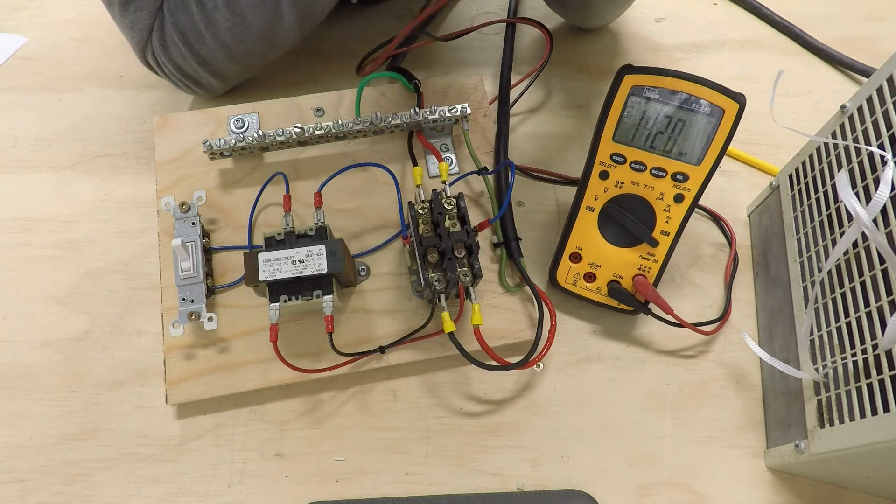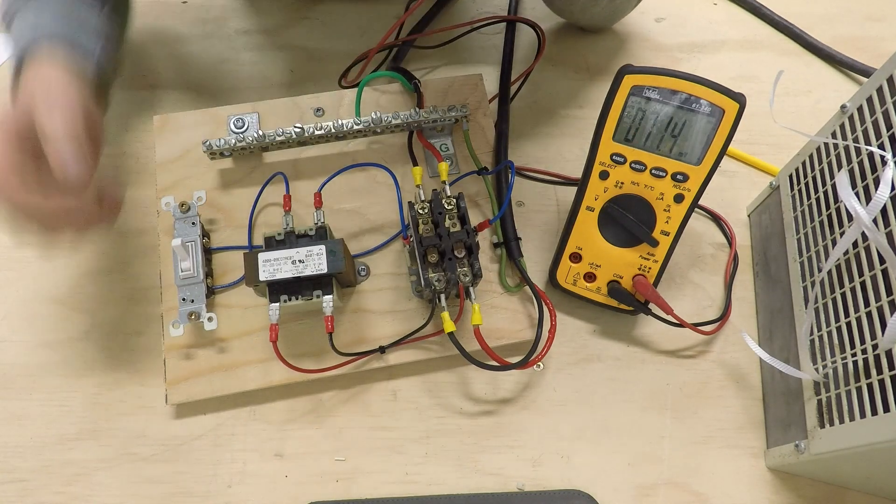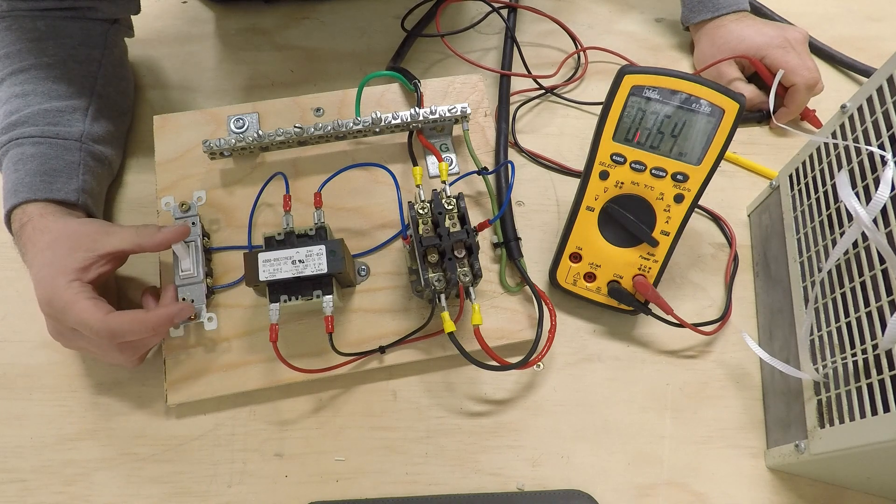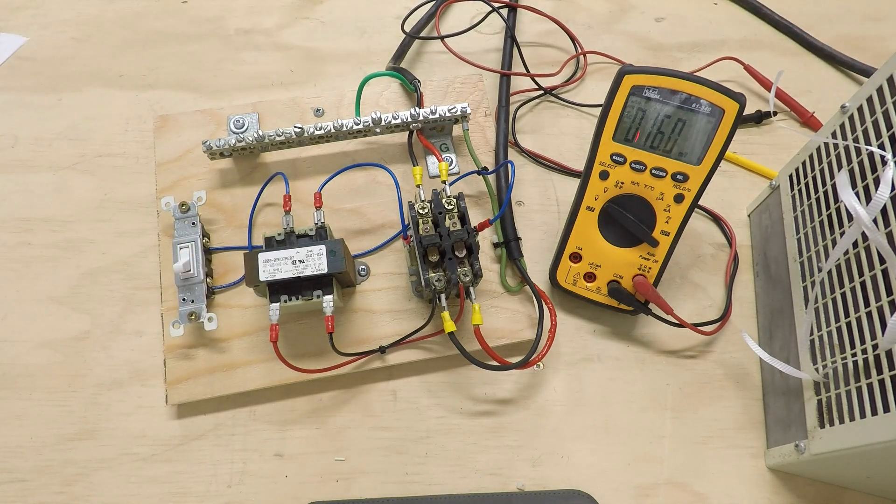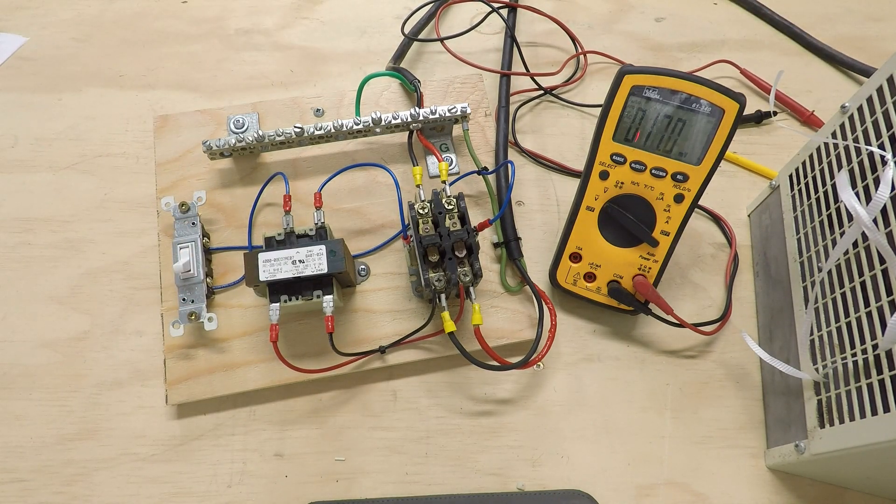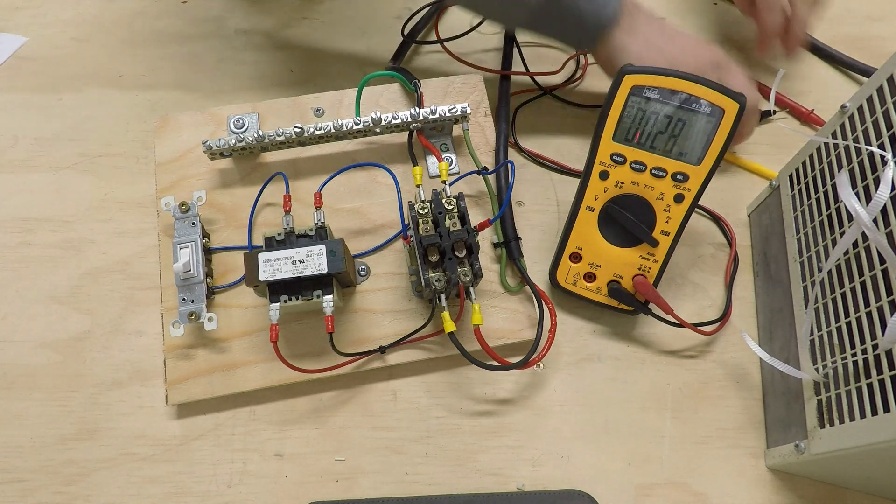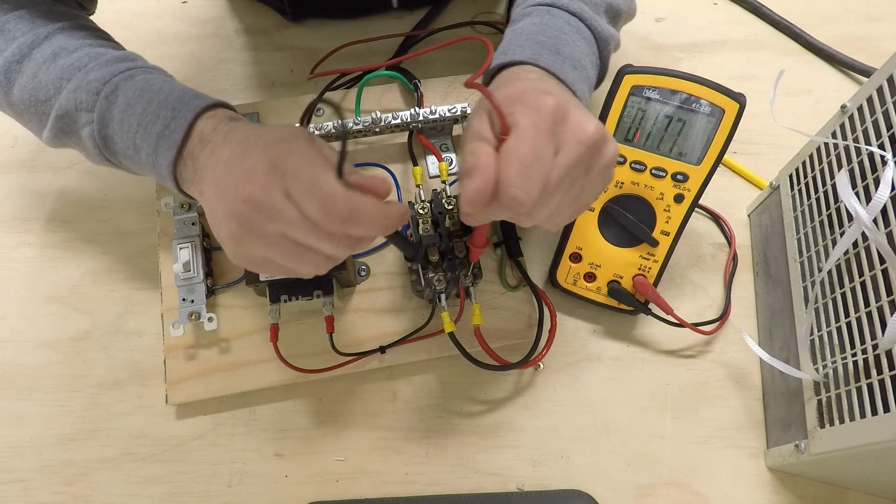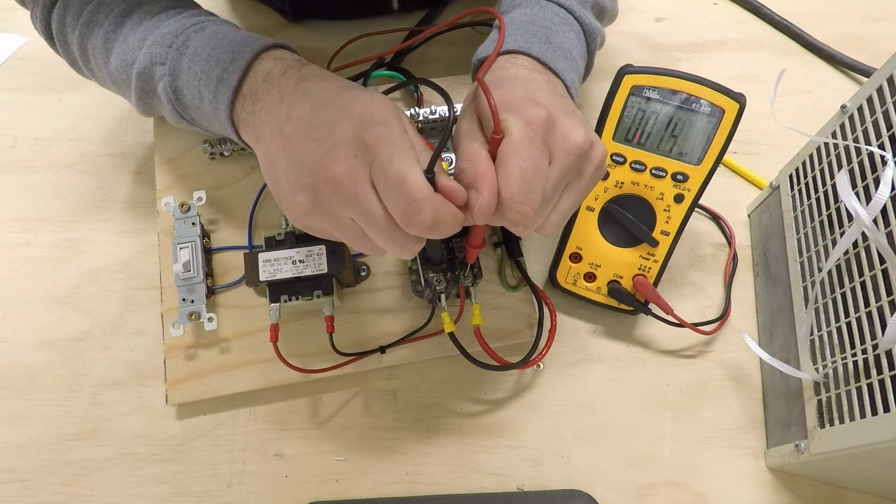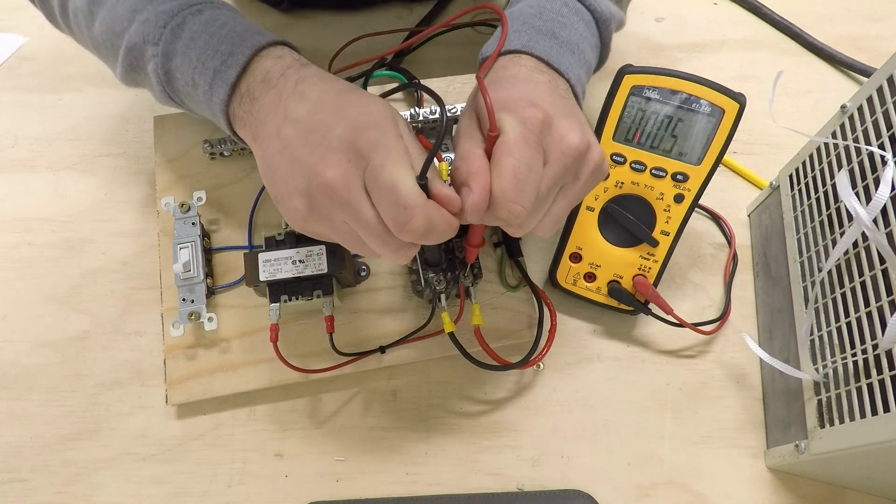So I'm going to show you how you can quickly fix that issue. So first thing you've got to do is turn off your contactor, and I'm also going to turn off the breaker. Okay, the breaker's off. I'm just going to confirm it because it's always better to be safe than sorry. And you've got zero volts on that. So perfect.